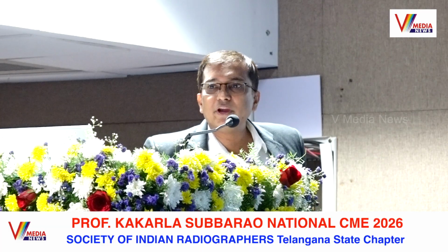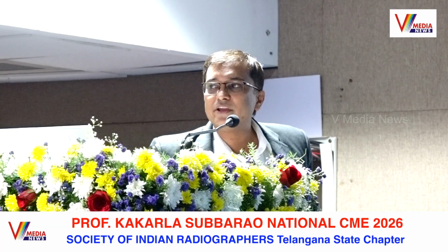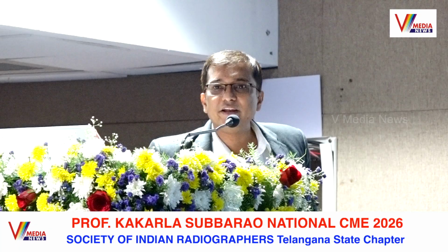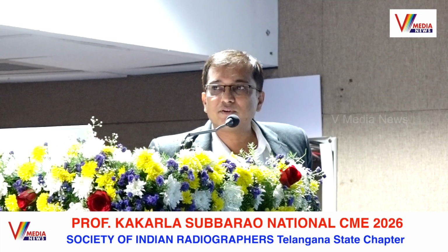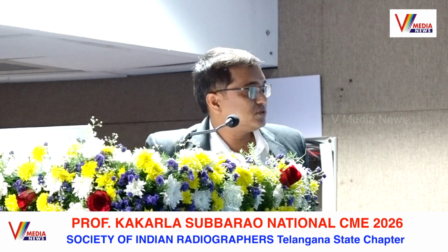For that, you must have quality checks, because radiation gives hazard, so quality should be checked. For example, if the machine has to give 70 kV and 10 ms, it must give 70 kV and 10 ms. For that, quality assurance is required, and there should be no leakage radiation either from the tubes, the lead barriers, the lead aprons, or the lead doors.